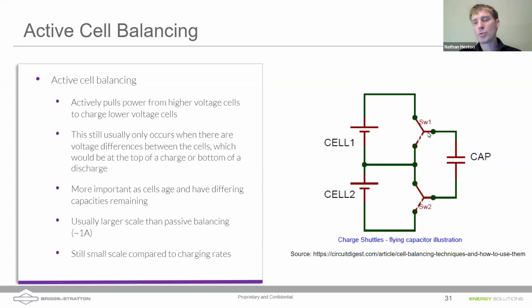But what you can do is have a switching device that's constantly switching between connecting the top cell to a capacitor and the bottom cell to the same capacitor. If we connect the top cell to the capacitor with the switches in the position shown, the capacitor would charge up to cell number 1. Then if we switch both of those switches simultaneously to the lower position, that voltage that was on cell number 1 would then be connected to cell number 2. If cell number 1 had a higher voltage, higher state of charge, the excess energy on that capacitor could be delivered to cell number 2 with very little to almost no energy loss.